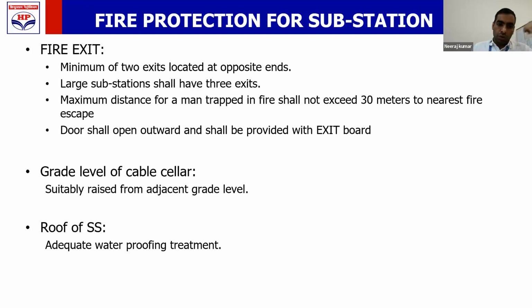Then at the design stage, you should also take care of the grade level of the cable cellar. Your cable cellar grade level should not be equal to or less than the adjacent grade level. You might have seen at many places, especially in Mumbai, that during rain water floods inside the substation cellar. Why it happens is that your substation cellar grade level is equal to or lower than the adjacent grade level. So your cellar should be at a higher elevation than the adjacent grade level.